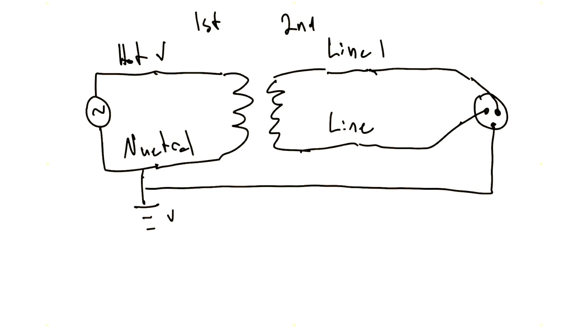So the key difference here between the second circuit and the first circuit is what? The neutral of our mains voltage is directly connected to the ground. Whereas in our second circuit, you'll notice line 2 here, which I forgot to label, is not connected to the ground. All right, so line 2 or line 1, neither one is connected to the ground. They are isolated, they are separate. Now, why is that important? Well, in this system, things function a little differently, right? In the first circuit, neutral and ground are connected. In the second circuit, they're not.